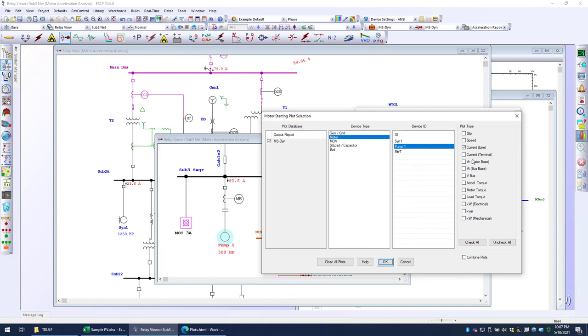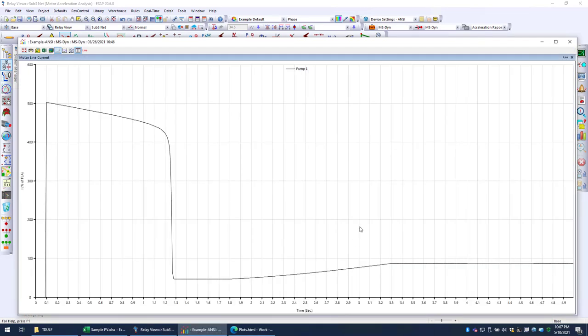the actual curve. So let's take a look at the current for pump number one. As you can see here, at 100 milliseconds, we see the lock rotor current, so approximately 500% of the full load amps. About 1 second later, this motor actually starts. It's partially loaded. That's why you see this ramp going up from about 40% loaded to about 90% loaded.